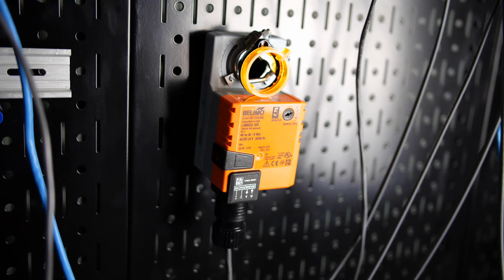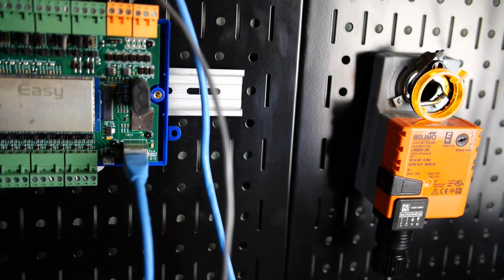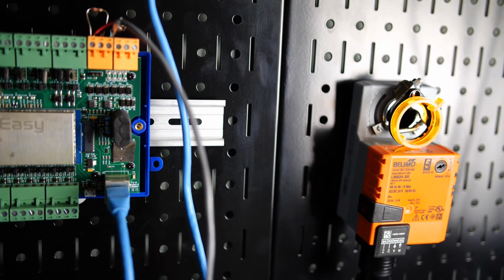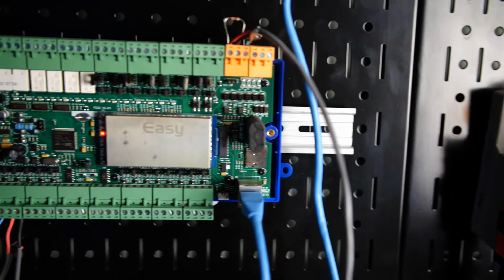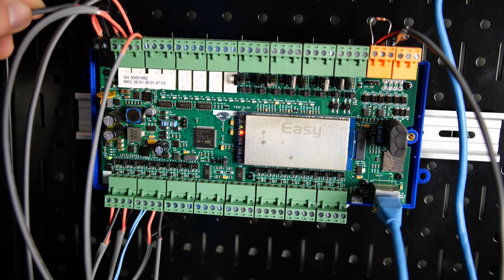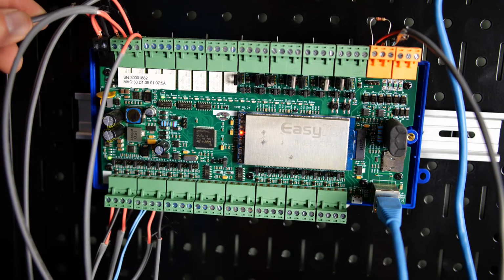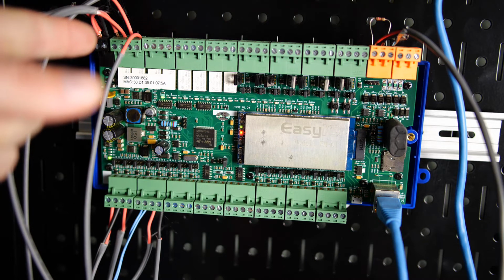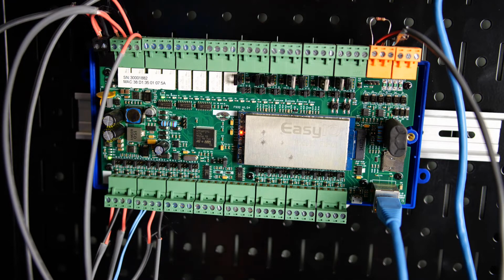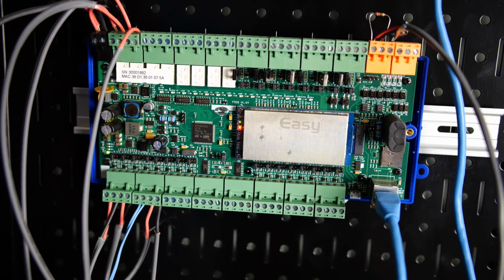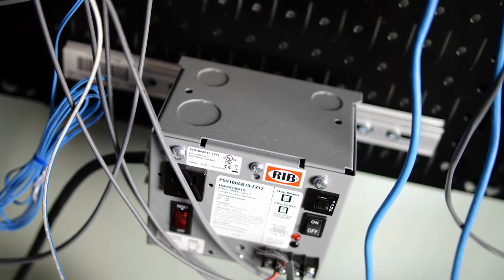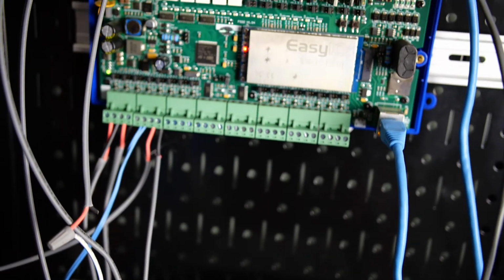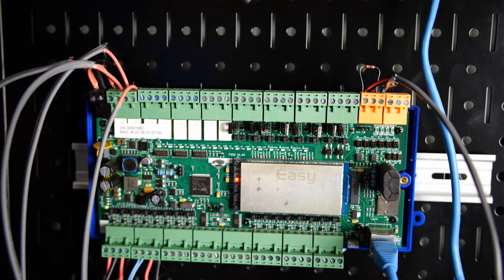But when I say shared commons, on our controller, I'm going to pan over to it a little bit right here. On our controller, you can start to see, can you see the power? No, you can't see the power at that angle. Now you can see the power. You can see our 24 volts AC power right here, okay? And that power has a hot and a common. So the common returns to the transformer, which is right down here. You can see the transformer. Okay, so the common returns to the transformer, and that completes a circuit.